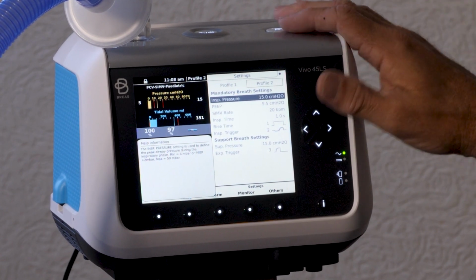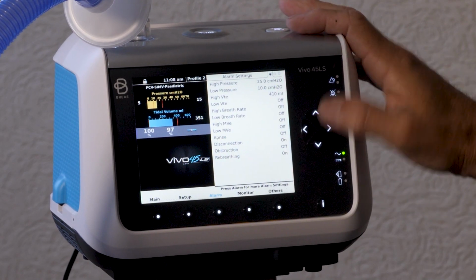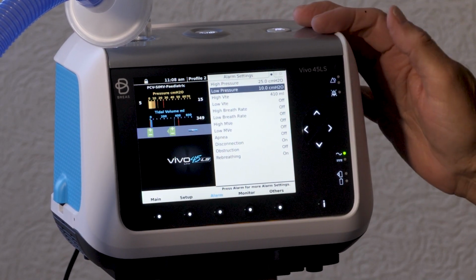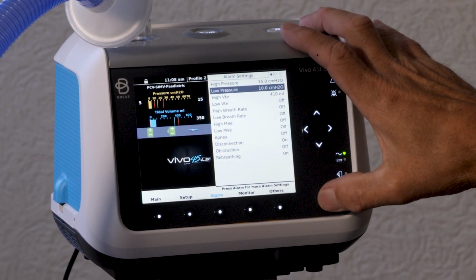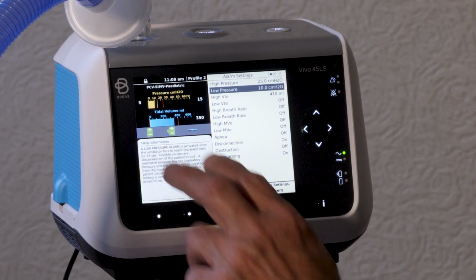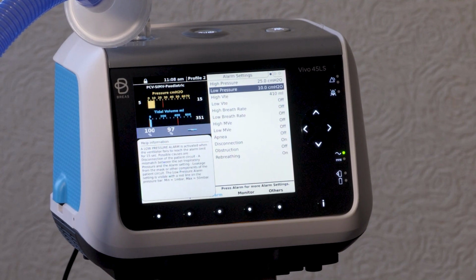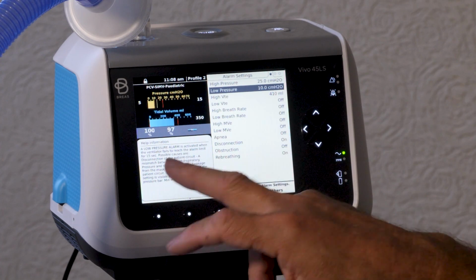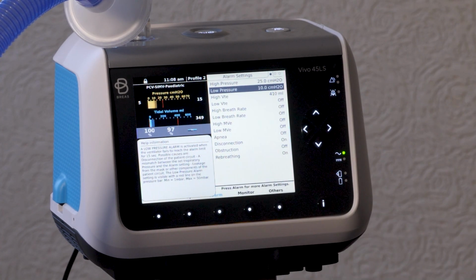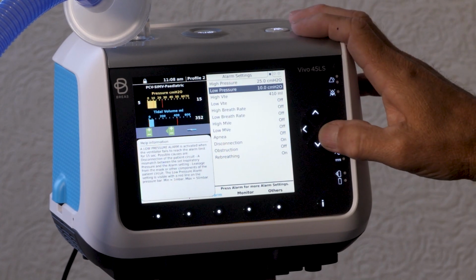It's new technology. And if we go back to the alarms and we highlight low pressure and hit the "i" button, now you have a description as to what that particular alarm is, when it's activated, and what the possible causes are of that particular alarm, which is very, very nice. Okay, we're going to continue on down.